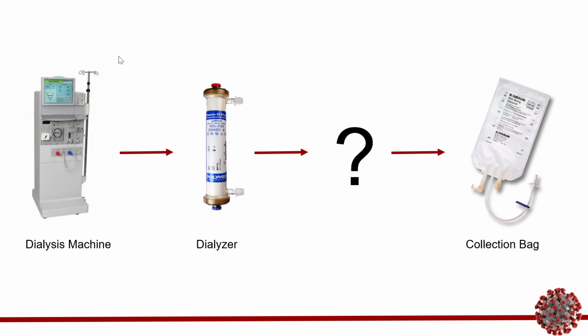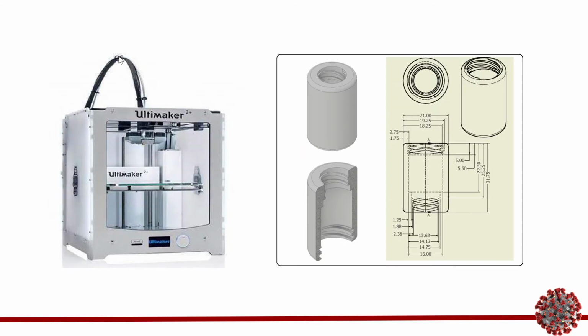This is when Dr. Parikh, one of our clinical mentors this year, reached out to the team of engineers for help. He asked us to develop a simple device that would allow the collection bags to be filled safely and efficiently. We immediately went to work designing an adapter to connect the collection bag to the dialyzer. We wanted this adapter to make this connection without contacting the dialysate so that it would reduce the risk of fluid contamination. Our design was simple, as the adapter is just a linear connector that allows fluid to flow straight from the dialyzer to the collection bag.